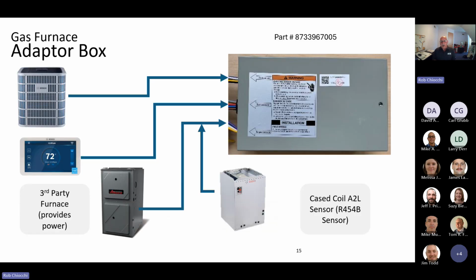Another product you're going to need to be aware of is dual fuel. Dual fuel with Bosch heat pumps is becoming exceedingly popular, particularly with third-party furnaces. So you can actually incorporate a Bosch IDS heat pump with a third-party furnace. However, you will have to avail yourself of this gas furnace adapter box to make that happen. The adapter box is the bridge between the leak detection system incorporated into the Bosch system, and it will allow that system to be used with a third-party furnace. So we will have these in stock as well.